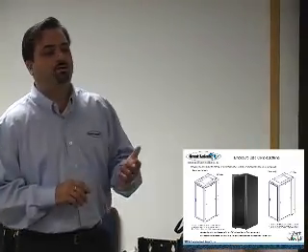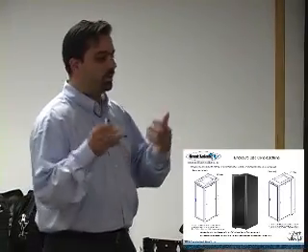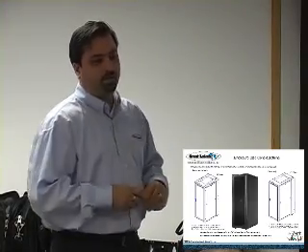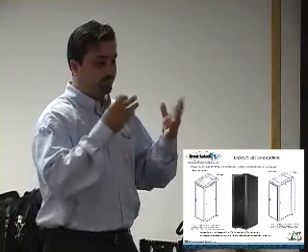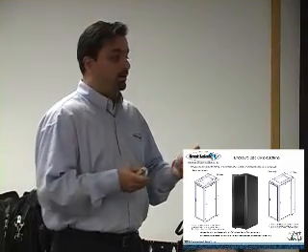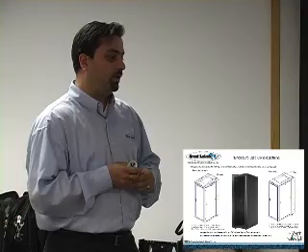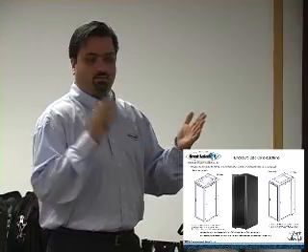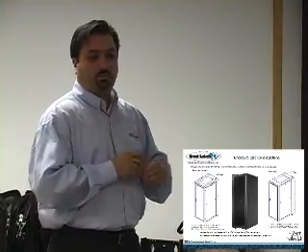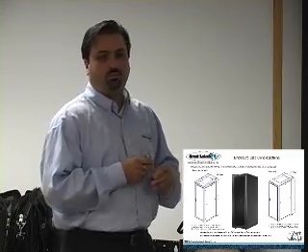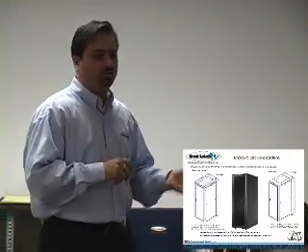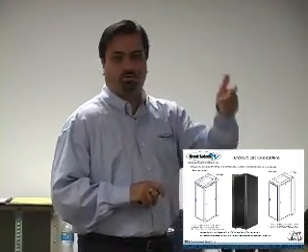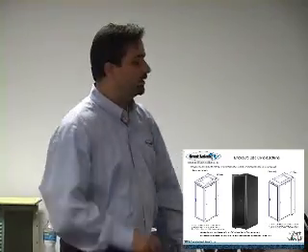your cooling and the exhaust. A lot of the equipment has cable bridges, and what we're seeing is people eliminating the cable bridge off the back and just letting everything hang down. That blocks the cabinet and creates a very large heat buildup in the back of the cabinet. You might not even know. In the cold aisle it might be 85, but right where the mesh exit of the door is, you're seeing upwards of 105 degrees, and you might not know. So I carry with me a little heat temp gun, and I just follow everything through, find the hotspots right there, and address them immediately.